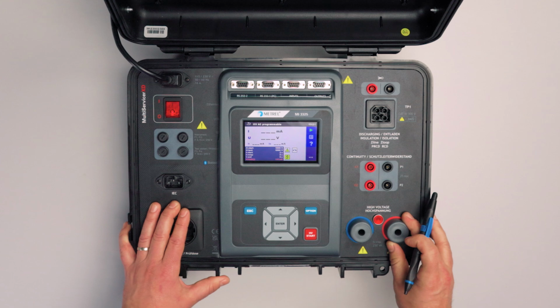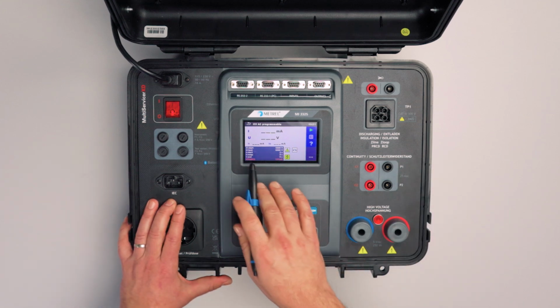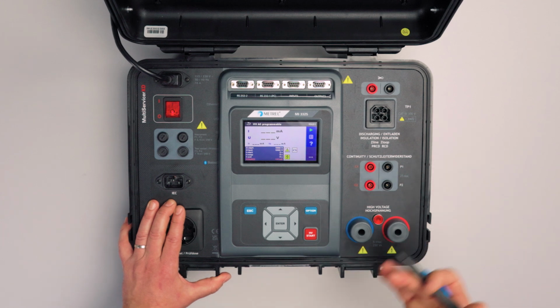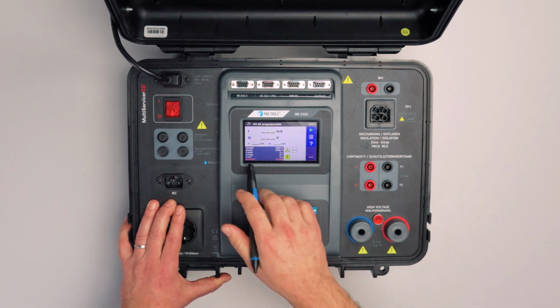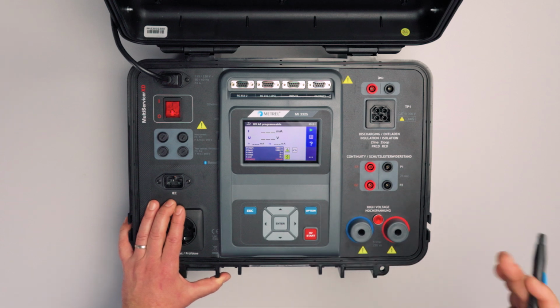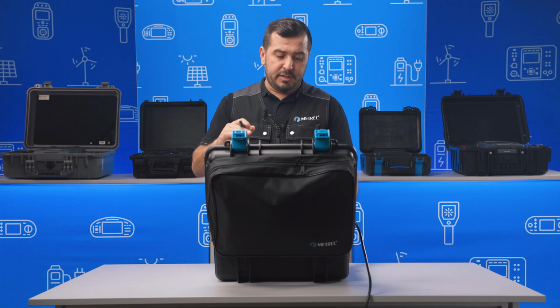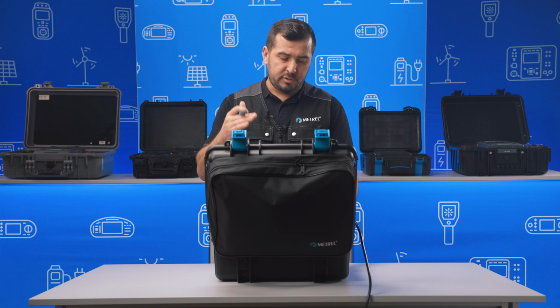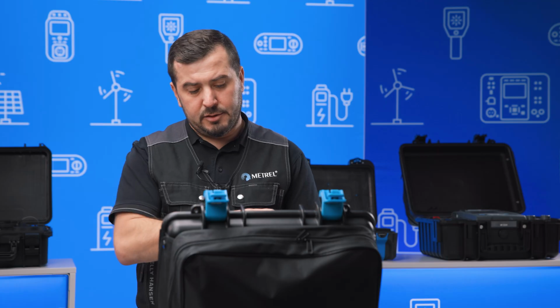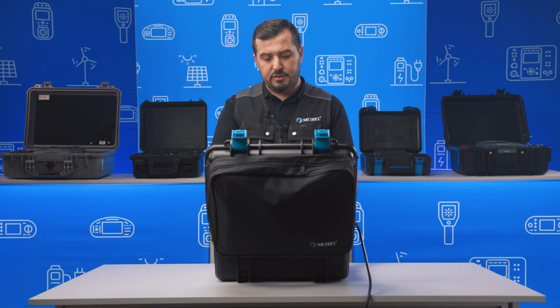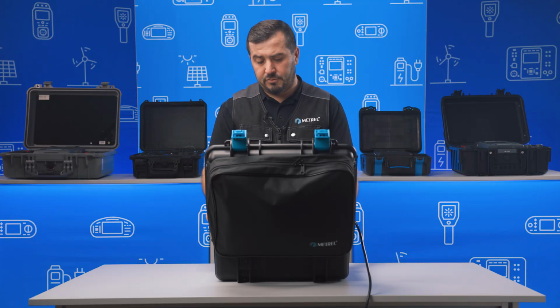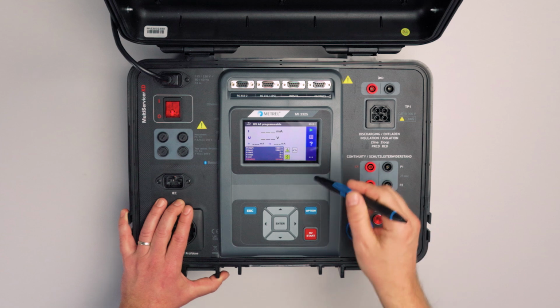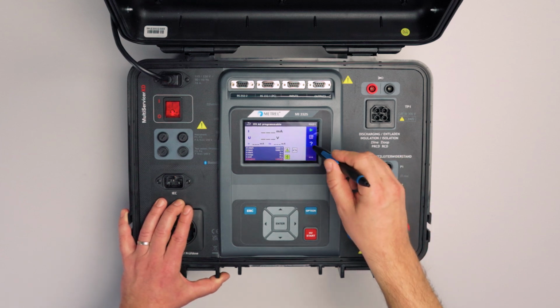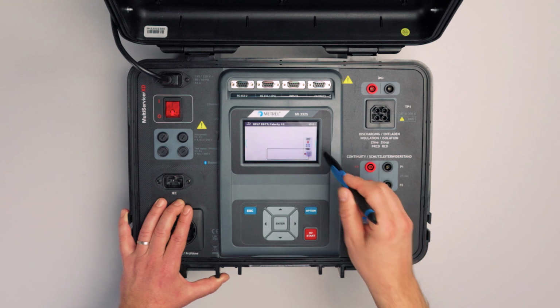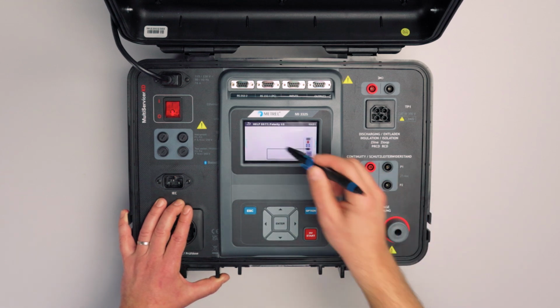The next option is the high voltage programmable one. Here we can set the starting test voltage and the end test voltage, and of course different times. One timer is set for the start voltage, then the second timer is set for the duration of the ramp, so between start voltage and the test voltage, and the last one is set for the whole duration of the test. If you would like to know something more about these functions or how to connect them, there are also always the help screens available.